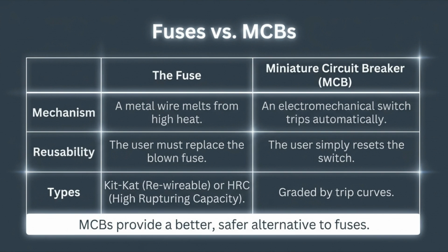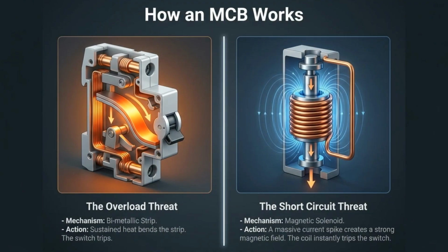While fuses melt and must be replaced, MCBs are electromechanical switches that simply trip and can be reset by the user. MCBs handle overloads with a bimetallic strip that bends from sustained heat, tripping the switch. For short circuits, a magnetic solenoid instantly trips the switch from a massive current-created magnetic field.